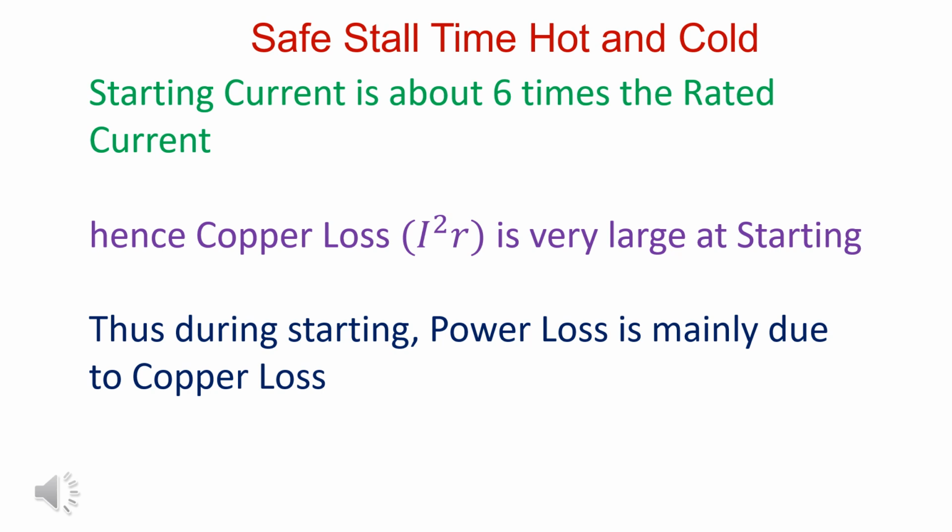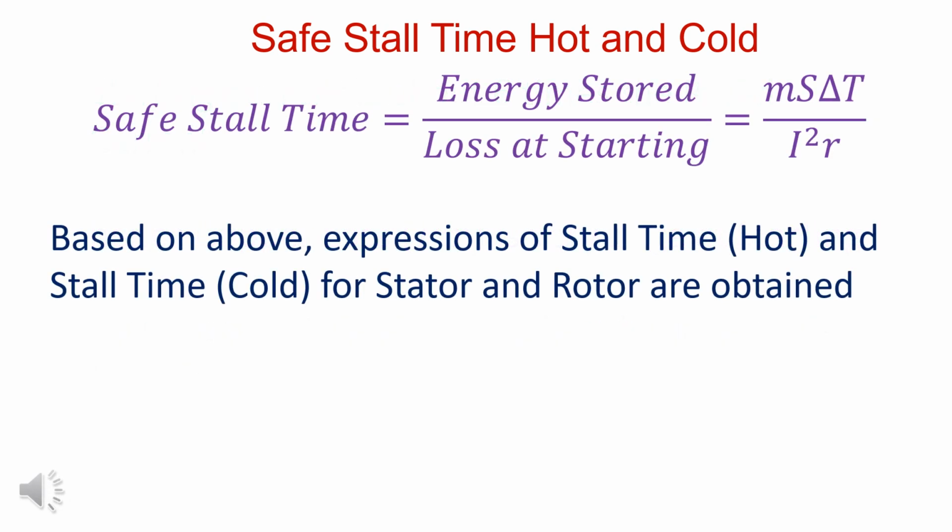Starting current of induction motor is very high. During starting, power loss is due to copper loss. Hence, stall time is equal to m S delta T divided by I square R loss. Based on this expression, safe stall time hot and cold for stator and rotor is obtained.